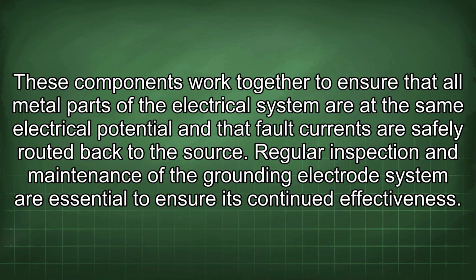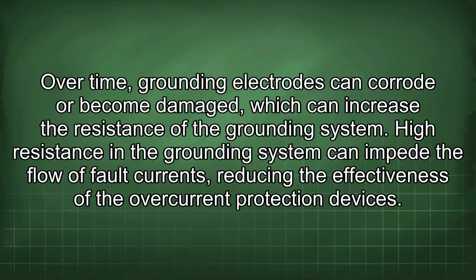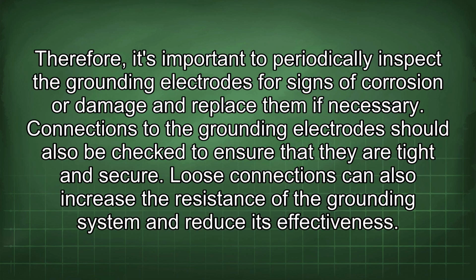Regular inspection and maintenance of the grounding electrode system are essential to ensure its continued effectiveness. Over time, grounding electrodes can corrode or become damaged, which can increase the resistance of the grounding system. High resistance in the grounding system can impede the flow of fault currents, reducing the effectiveness of the overcurrent protection devices. Therefore, it's important to periodically inspect the grounding electrodes for signs of corrosion or damage and replace them if necessary. Connections to the grounding electrode should also be checked to ensure that they are tight and secure. Loose connections can also increase the resistance of the grounding system and reduce its effectiveness.